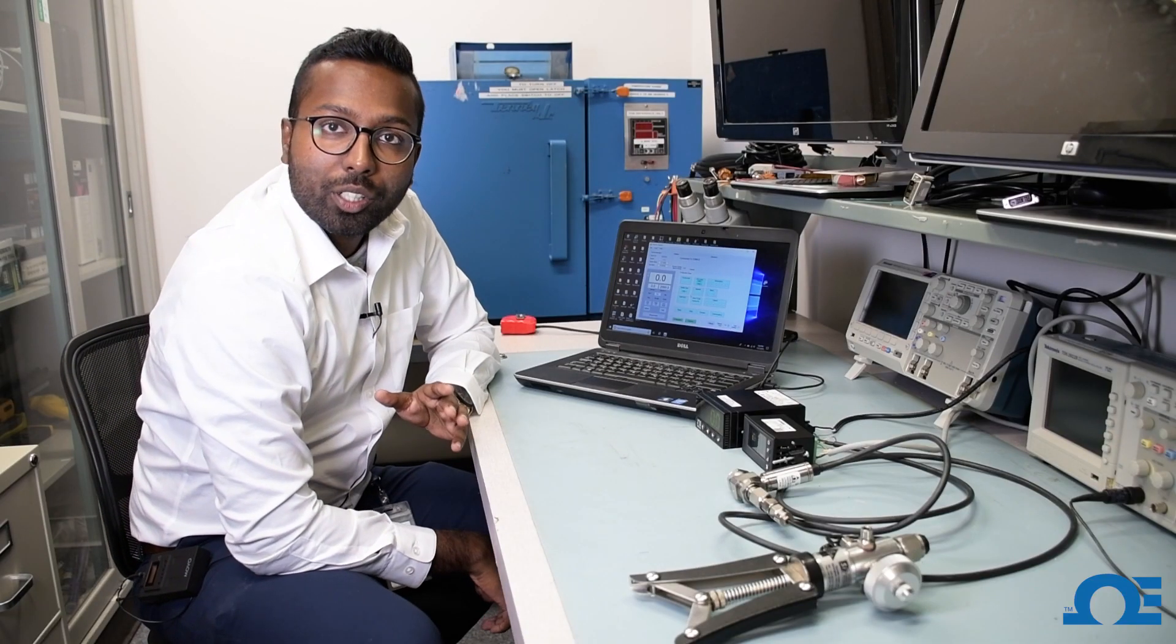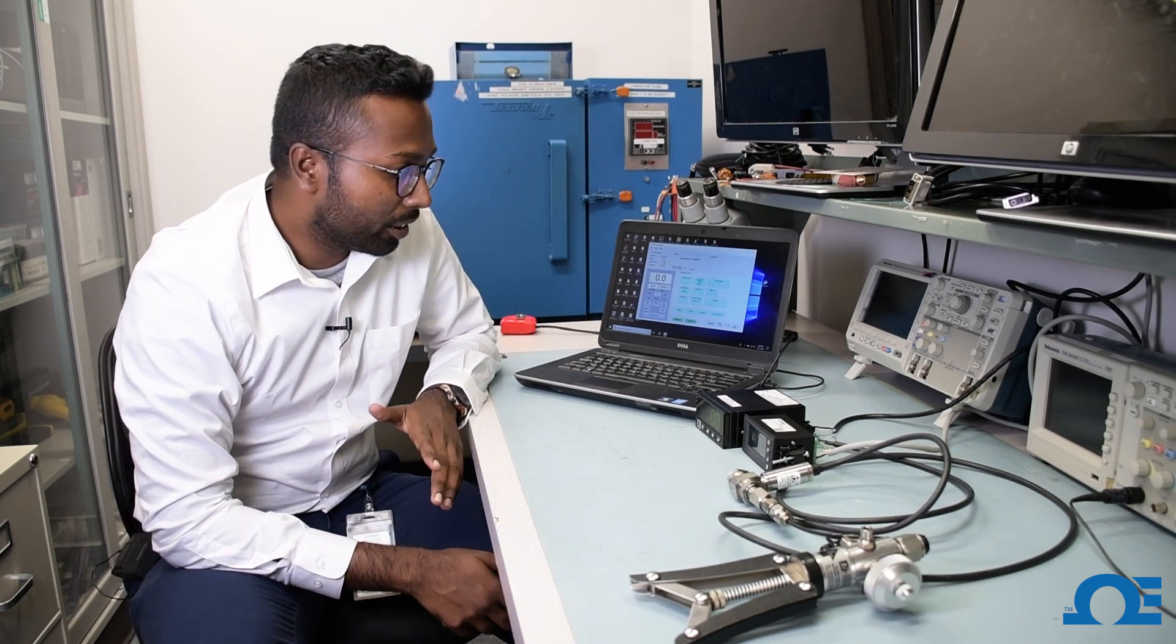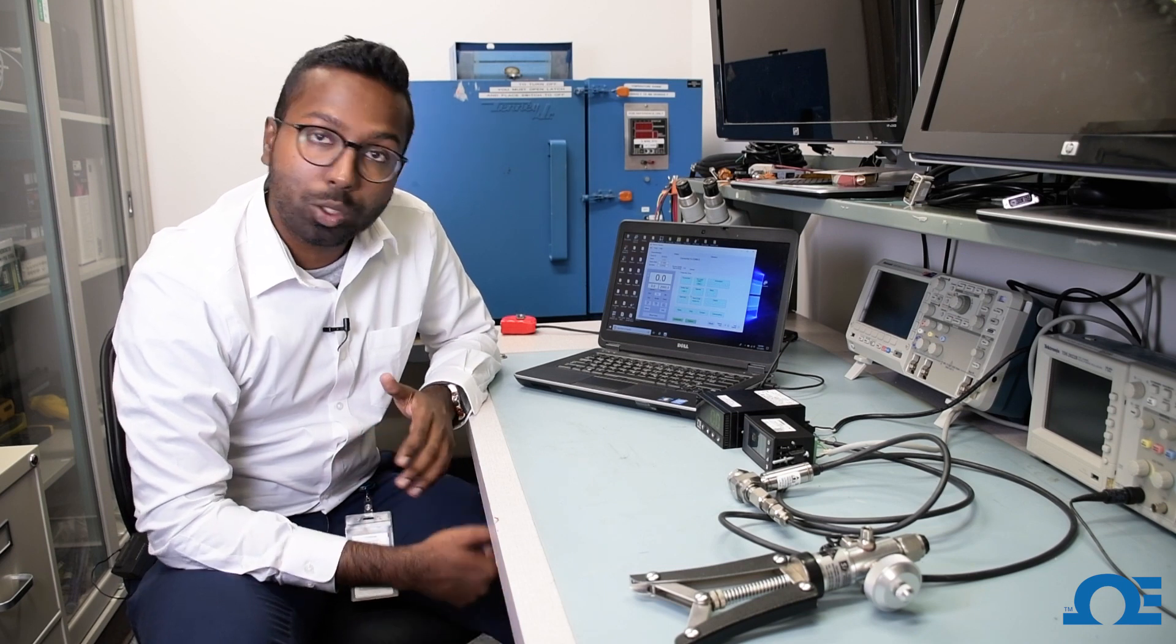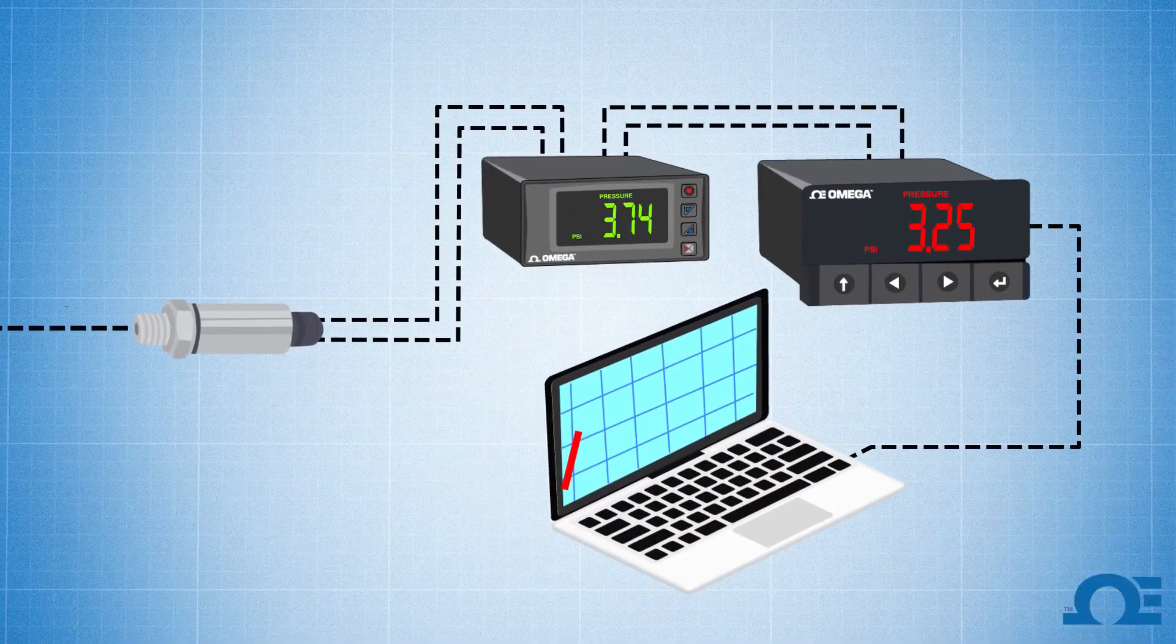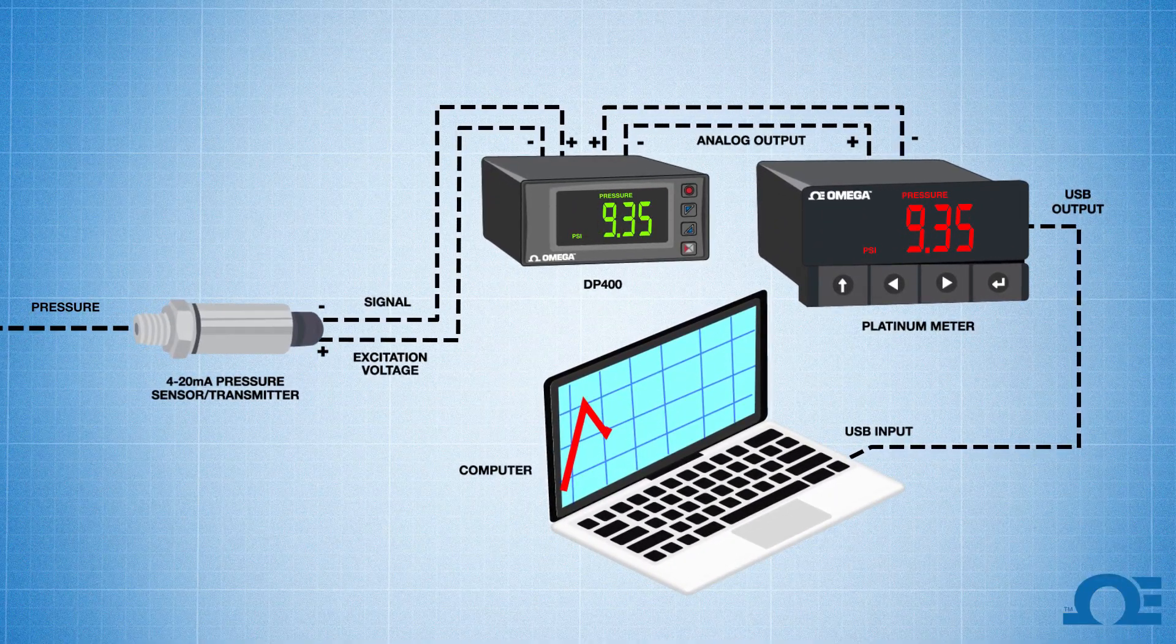So let's say you have a pressure transducer that puts out a milliamp output. Milliamp signals are typically connected in series to multiple devices, so it makes it super easy for connecting a milliamp signal device to multiple instrumentation units at the same time.